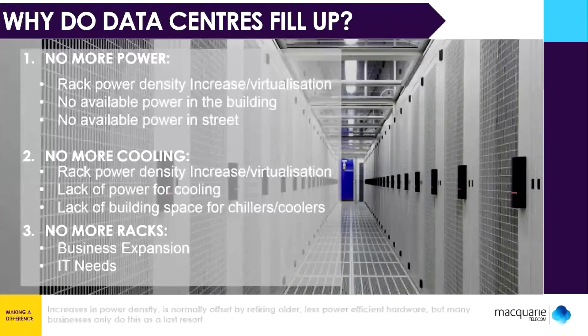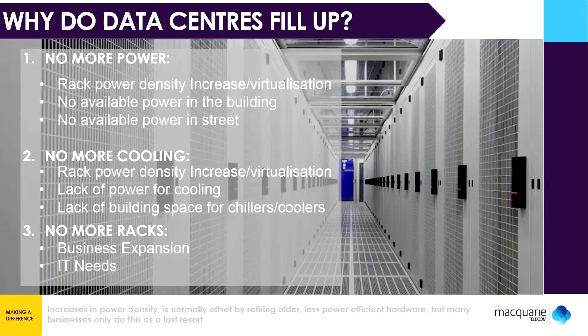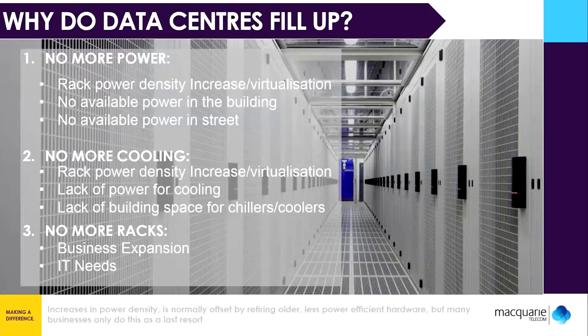So let's look at why you might extend your data center, and think about the reasons why data centers start to get full. The most common thing we hear from corporate IT businesses around Australia is the lack of power. In our first data center, we engineered the site to carry 1.5 kilowatts per square meter — that was about 10 years ago. Just recently, our IntelliCenter 2 data center increased from 1.5 up to 3.5 kilowatts per square meter. That's a major change — all of the wall space is now taken up with power boards and breakout boards, and the underfloor cabling is huge compared to many years ago.